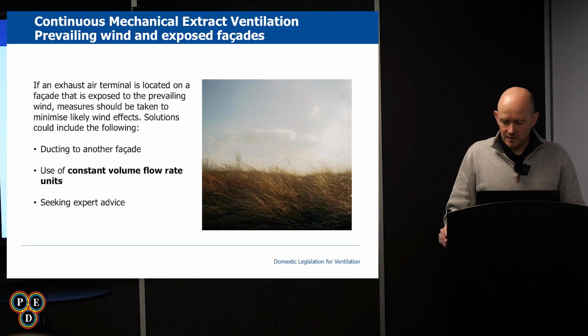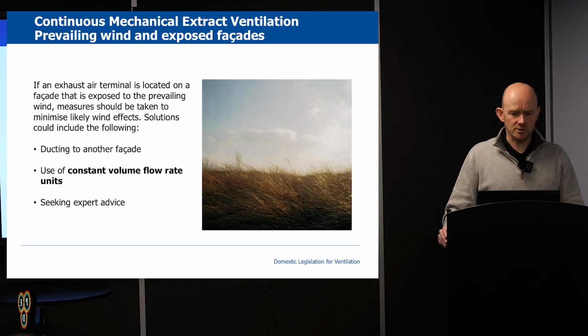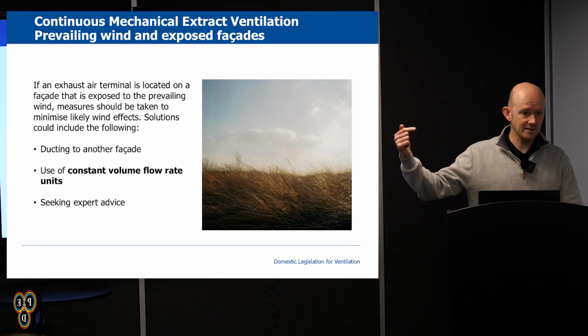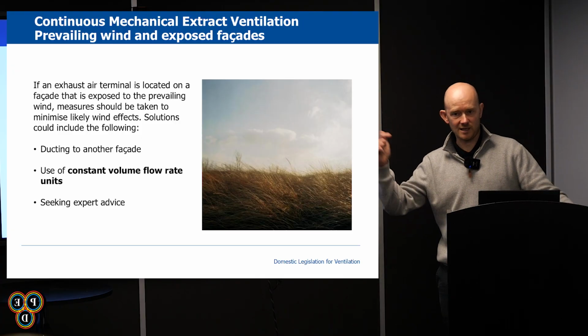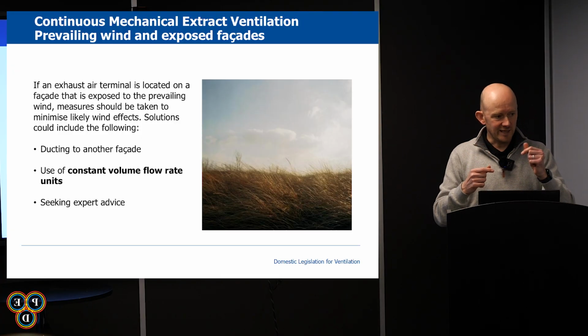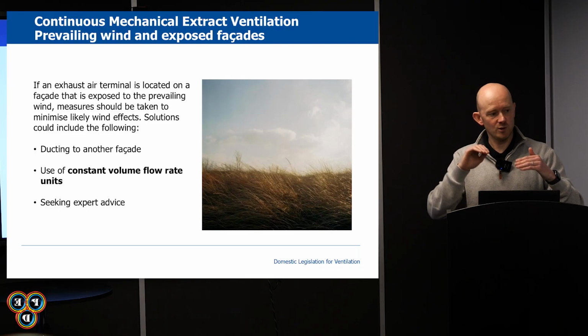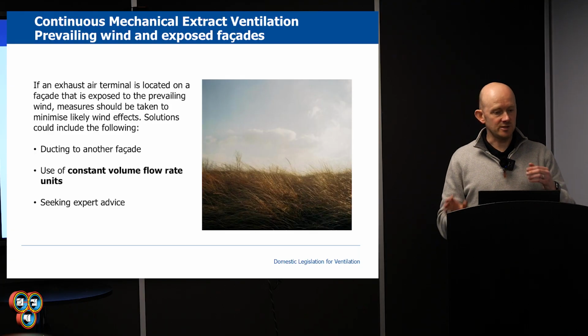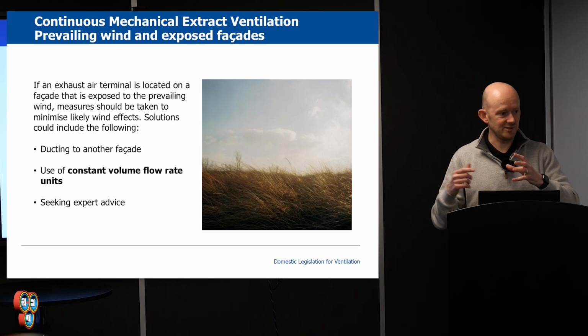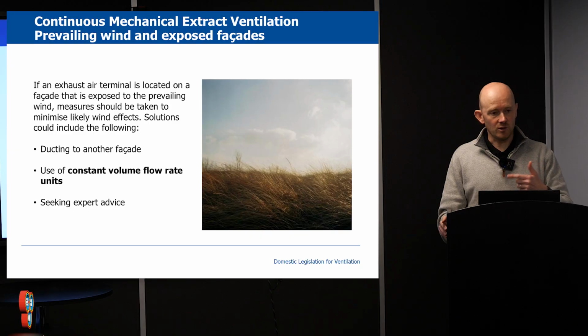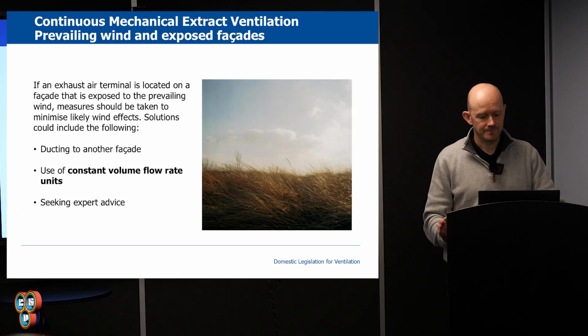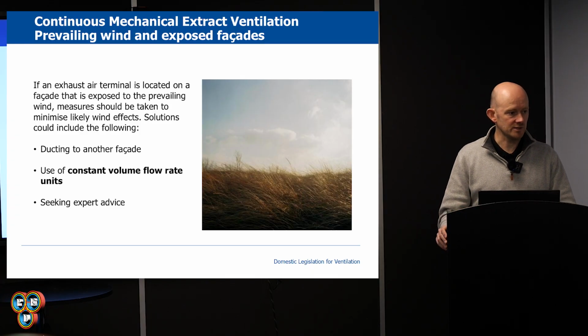A point to consider is prevailing wind and exposed facades. This can be combated with any of these 2 points. The best solution is to use constant volume fan units. Do you know what a constant volume fan is? So constant volume fan is a fan that can detect driving wind. So if you've got a fixed grill and the wind's coming off the sea and hammering at the grill, the little EC motors in there would struggle to push harder than a 60-mile-an-hour wind. It would just stop. You'd actually see the fan impellers stop because the wind's stronger than what the fan can do. But if you get a constant volume fan, it can detect the pressure and it speeds up to maintain the extract rate. It's not on everyone's DMEV, but it's on some people's DMEVs.